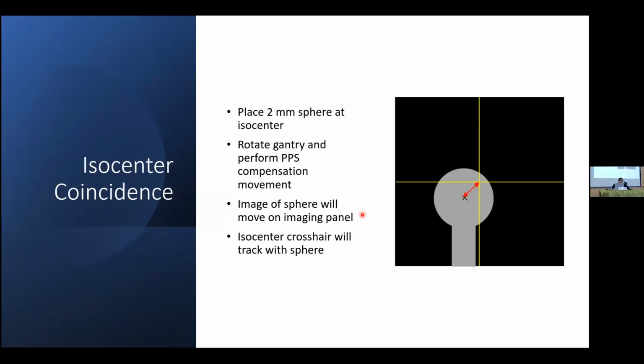And then the final is the true isocenter, when you get all the things placed together, mechanical and radiation. So I was saying at different gantry angles, the radiation slightly changes. Some vendors want to correct that with the couch. There's that kind of correction, or you can correct it with the scanning magnets or steering magnets. So knowing how your vendor is actually going to correct that matters, because of how you're going to then prove that it's actually going to the right place. And if something changes, are they still using the same mechanism, and is it reproducible?